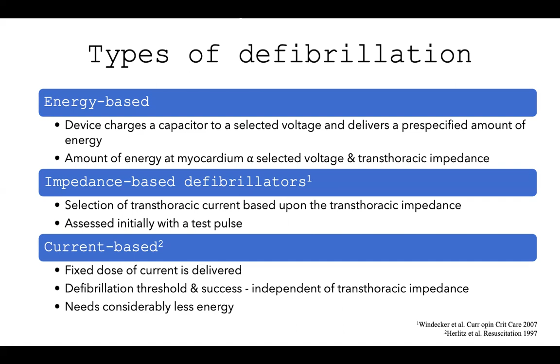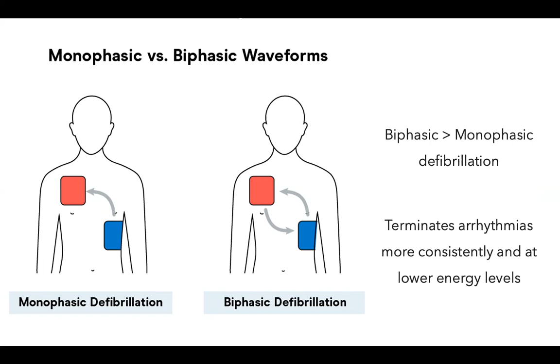Beside it, we are aware of monophasic and biphasic waveforms, depending on the direction of the current. In monophasic waveform, current moves in one direction, and in biphasic defibrillation, current moves in both directions. Though monophasic defibrillation has a significantly high success rate, biphasic defibrillators are better in terms of termination of arrhythmia. They terminate arrhythmia more consistently and at a lower energy level.